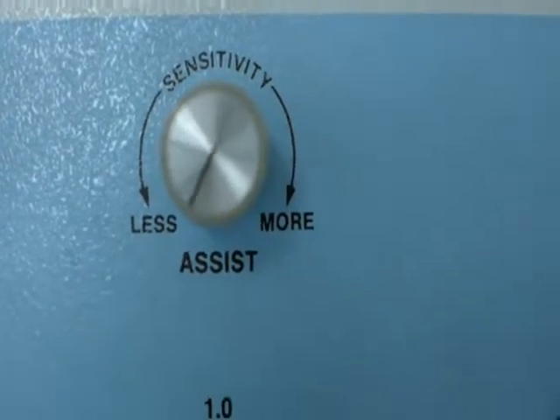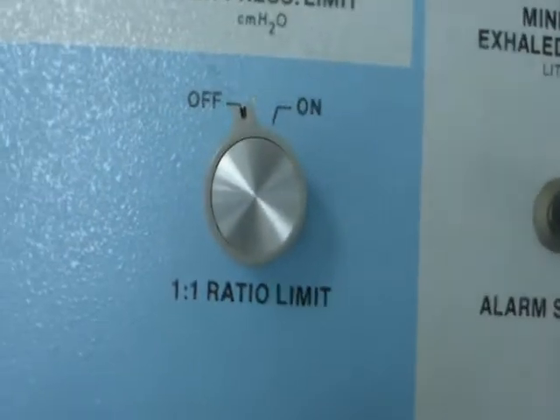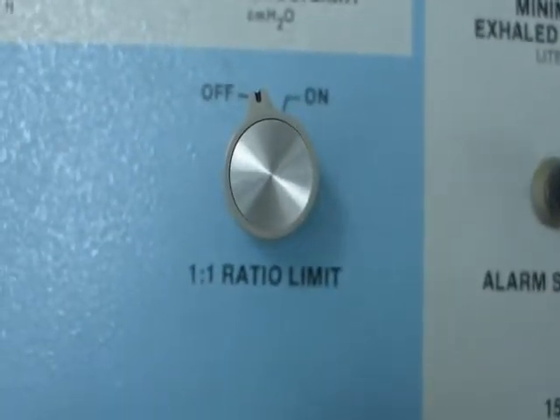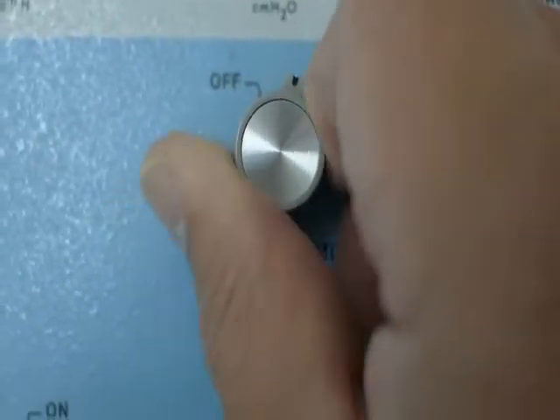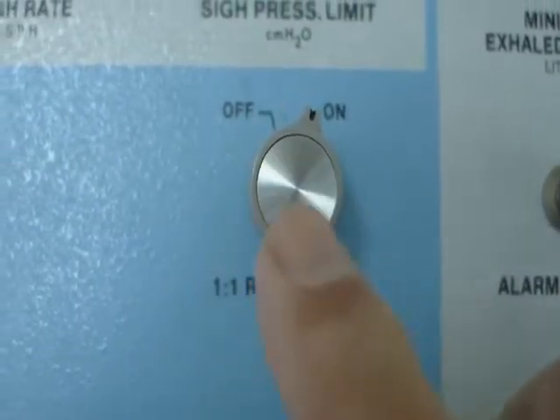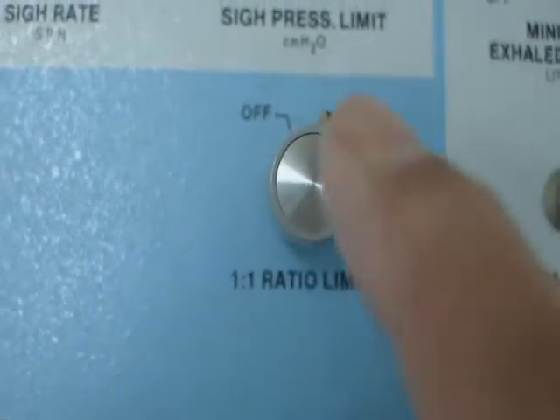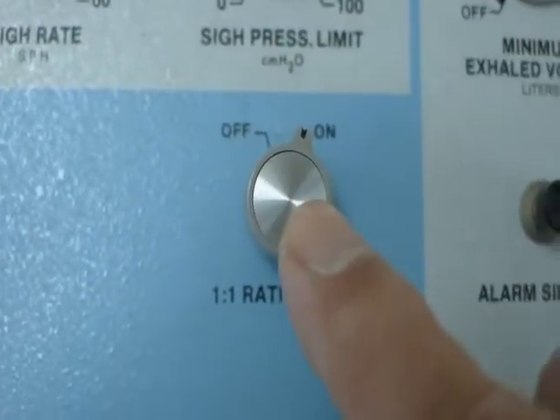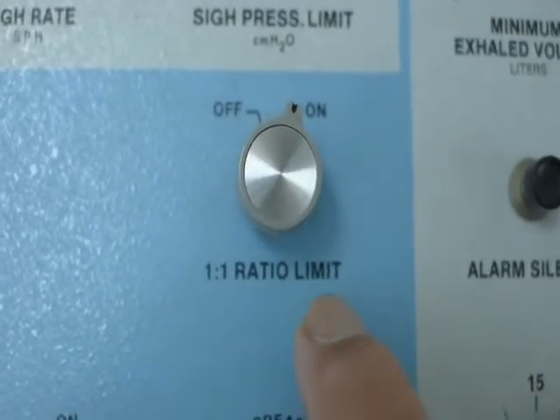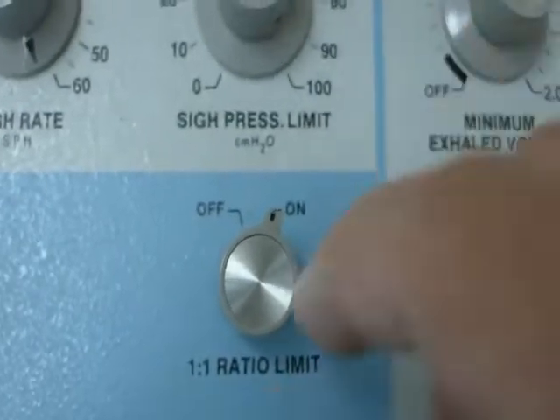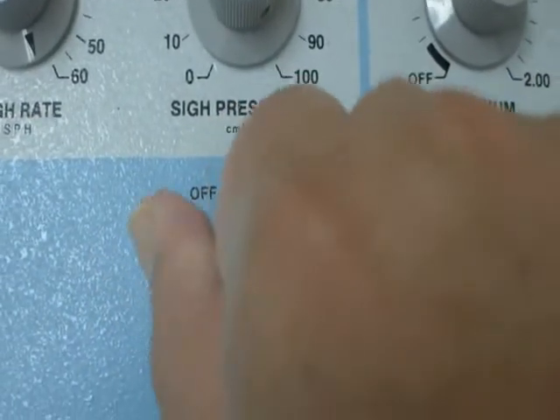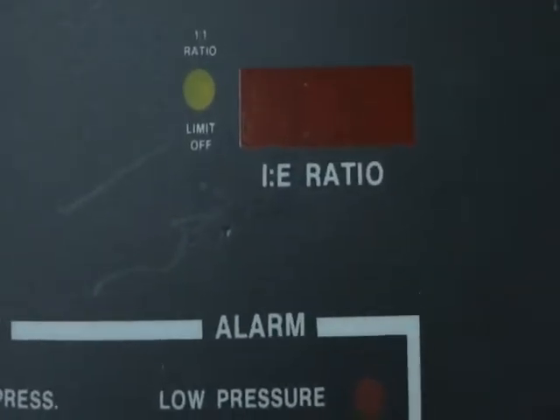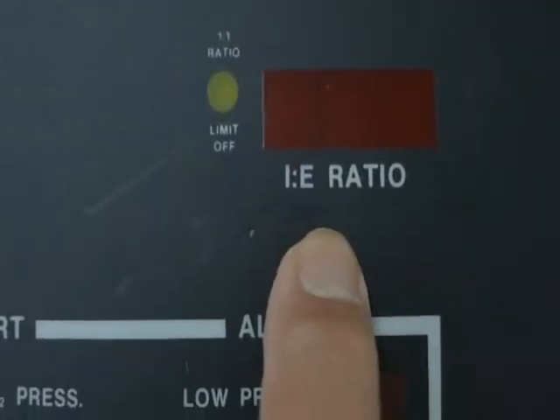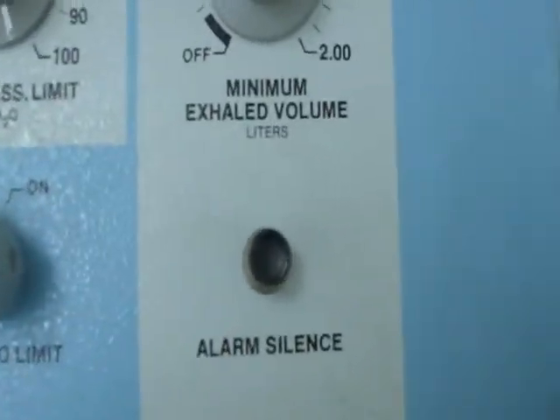Okay. So now when we come over here is the IE ratio. So this is the IE ratio limit here. We can turn the ratio limit on and off here. That activates this 1-to-1 ratio limit. And then anytime we turn it on and off, it will affect the IE ratio display on the top over here. Okay. And then we come down here.